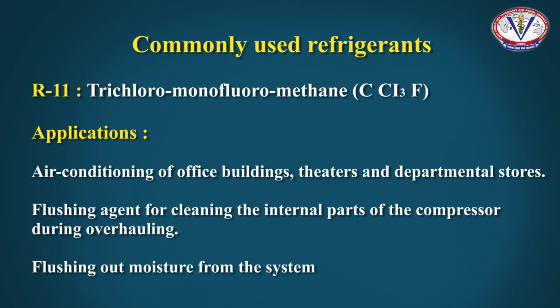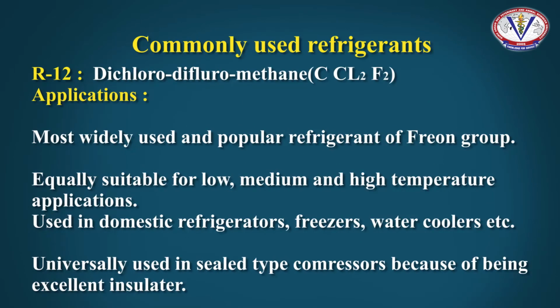The commonly used refrigerants under halocarbon compounds, the first one is R11 or trichloromonofluoromethane. Application wise, these can be applied for air conditioning of office buildings, theaters and departmental stores, and as flushing agents for cleaning the internal parts of the compressors during overhauling, and flushing out moisture from the systems. Next refrigerant in this category is R12, that is dichlorodifluoromethane, that is CCl2F2. Application of R12 includes: the most widely used and popular refrigerant of the freon group, equally suitable for low, medium and high temperature applications, used in domestic refrigerators, freezers, water coolers, etc., and universally used in sealed type compressors because of being an excellent insulator.